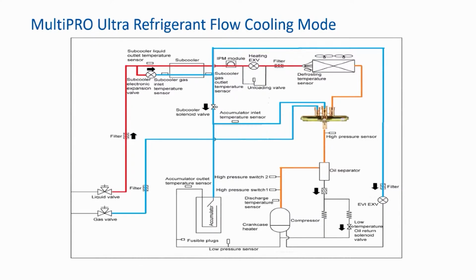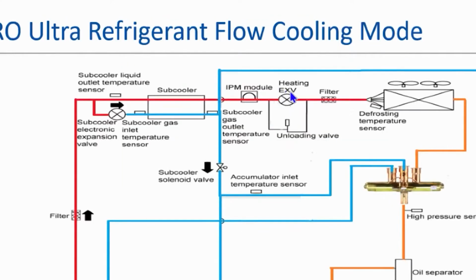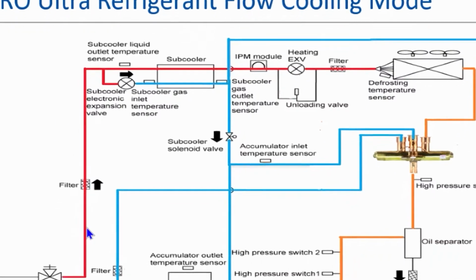This is the new GMV6 MultiPRO Ultra. As you can see, and that's why I'm pointing this out so you guys can follow along, here's your outdoor coil. Here's that EEV that I was talking about again. Same thing. If that EEV is not all the way open, now you guys got an unloading valve here, but still, if this EEV is not open at full 480 steps during a cooling cycle, we're going to go into pump down because we don't have any liquid refrigerant feeding out. It'd be no different if I close this service valve. So if that EEV is not working, or if the coil is not on the valve body, just like the one I ran into, you're going to have that same exact scenario.